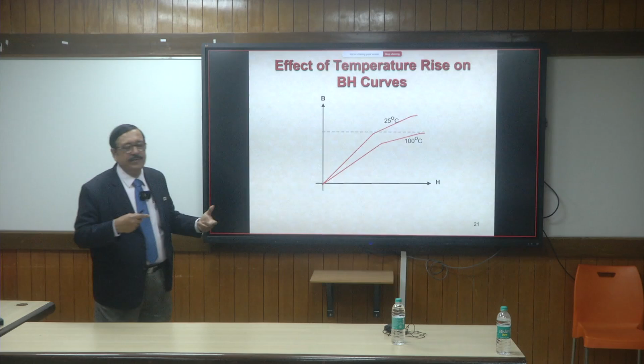So you have to always take the BH curve at the higher temperature while designing and not at the lower temperature. Otherwise you'll have unprecedented magnetic problems in your design, because your core is going to run hot. Whether the core itself generates heat or the coil over the core generates heat, it's one and the same. The core is going to get hot because of either one of these two reasons. And so you have to be very careful.